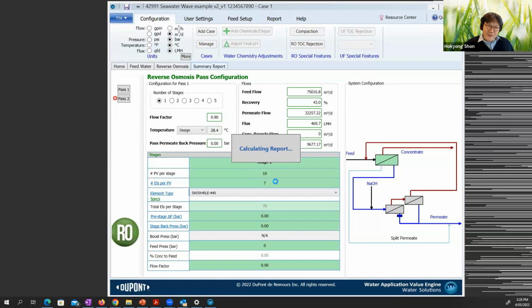So that's why I changed this value. It's not going to work, there are not enough pressure vessels. Exactly, that's what it is. It shows not enough. That's why you have to start with small scale, which we already practiced manually, and then go a little bit higher, and a little bit higher, and then calculate. That way you can get more confidence in your design, because this is one example. So you can make your own simpler and better design of your RO membrane systems.